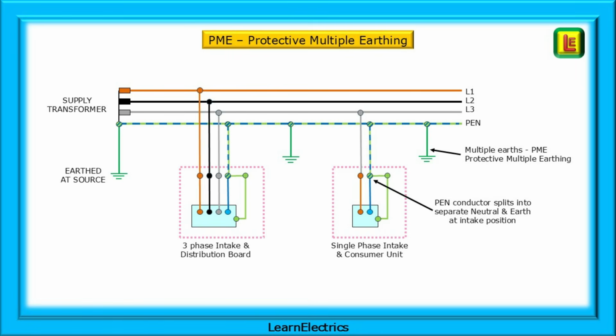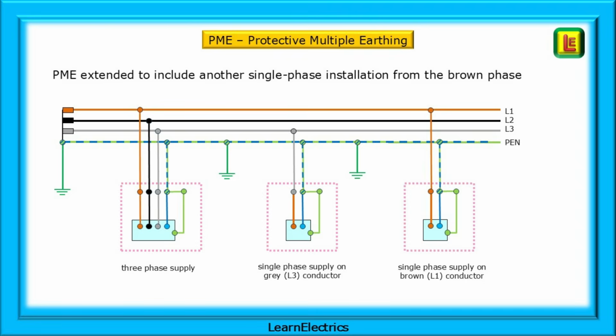At the intake positions, the PME cable is divided into a separate neutral and a separate earth, never to be joined again. Notice at the single-phase intake position, it is the grey L3 phase that comes into the property. But after the DNO's fuse and break out, the colour changes to brown, as we usually expect to see in single-phase and domestic installations. A PME earthing system is easily added to or extended as shown here.